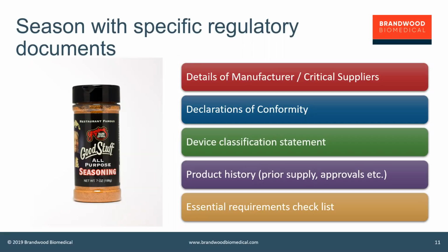And then the last one is the essential requirements checklist. Again, the content of these between Europe and Australia aren't tremendously different. There is a different template, there is a different nomenclature to them. EP checklist in Australia, ER checklist currently with the MDD in Europe, moving to the GSPR, I believe. The content of those are not completely unique.